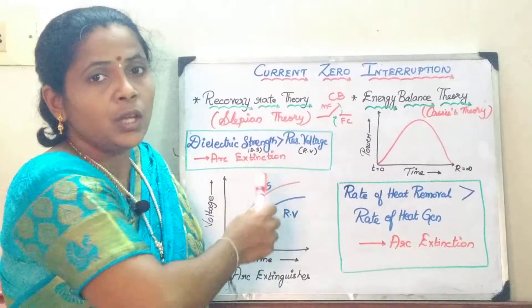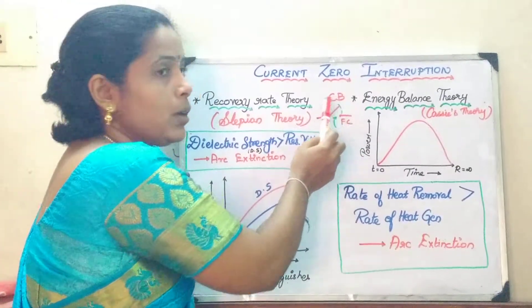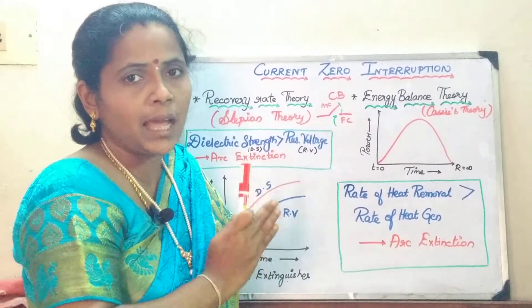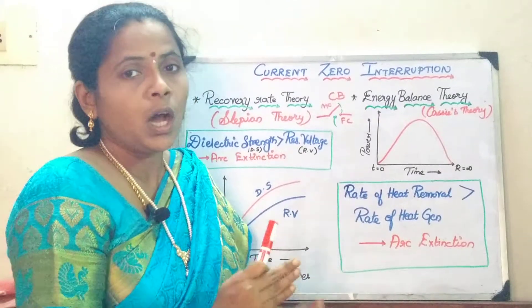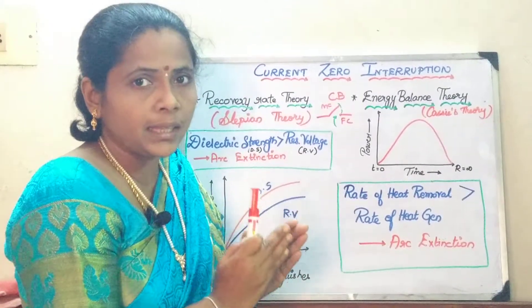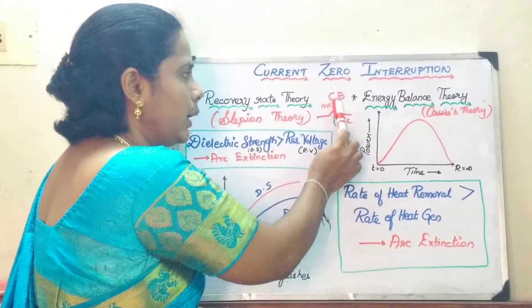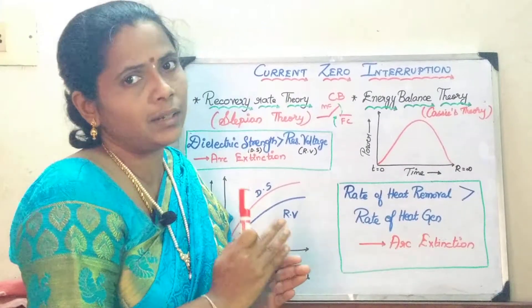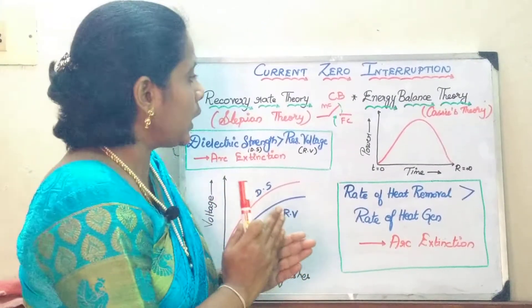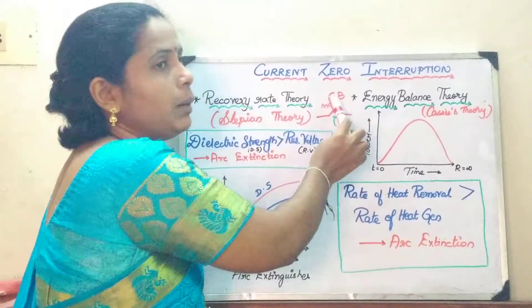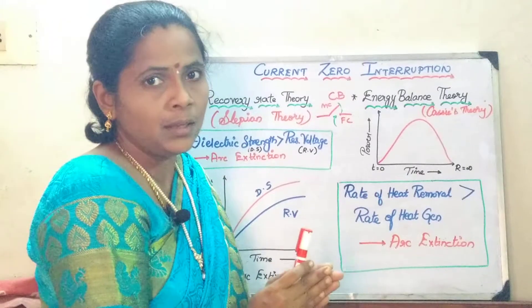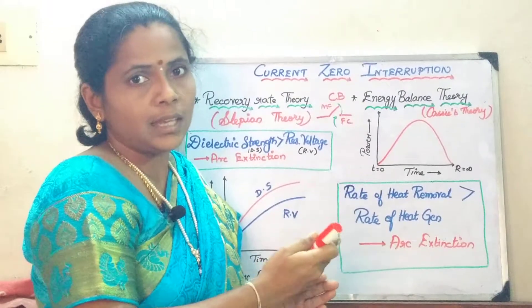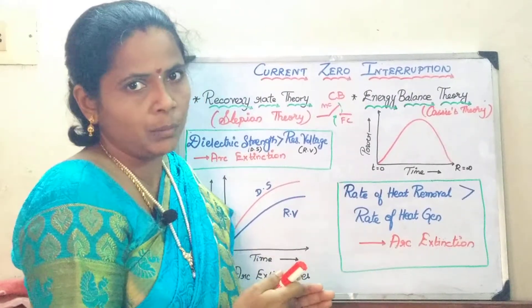In the Slepian theory, whenever you have arcing — whenever the contacts are open — the main criteria is that the arc has to be interrupted as soon as possible. Whenever arcing occurs, you apply a cooling medium to quench the arc, and it should be done as soon as possible to avoid damage. What we do is remove the ionized particles from the arc path, so that the resistance of the arc gets built up — that is, the dielectric strength gets built up — and the arc will get extinguished as soon as possible.